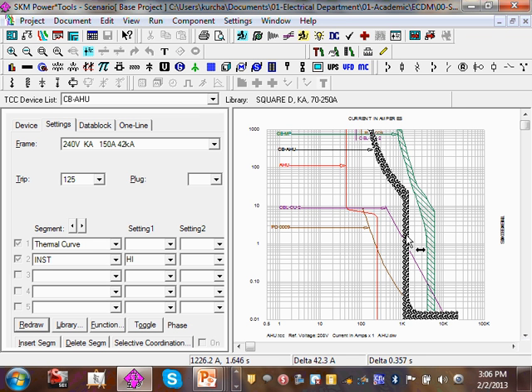No need to push it all the way, because I just want to make the air handling unit start so I can push it back. Too low, right? So all the way. Now, if I have a short circuit right here, instantly my circuit breaker will trip. And that's what you want. Otherwise, you expose your people to a huge amount of arc flash.